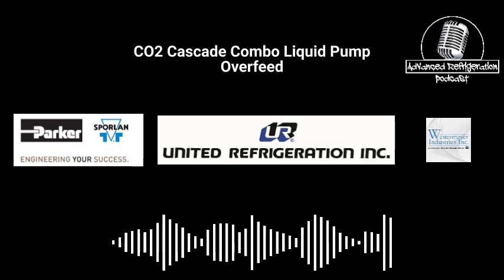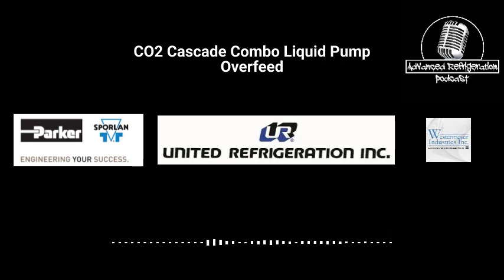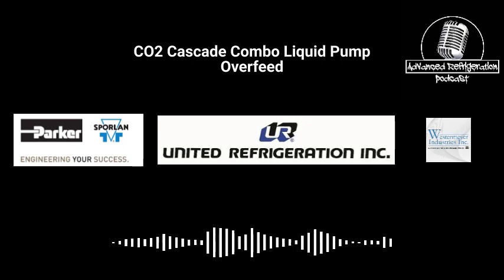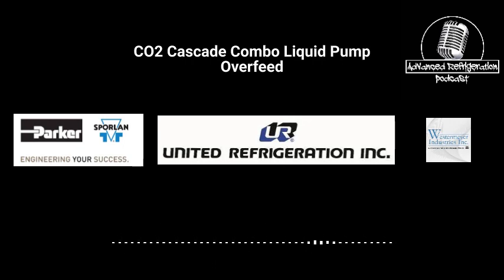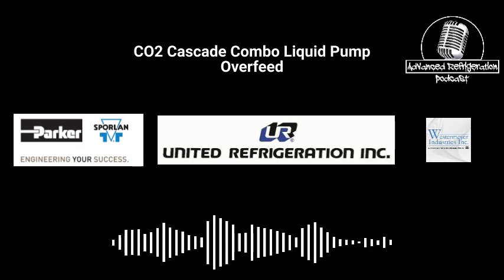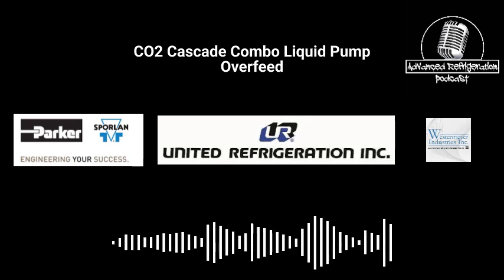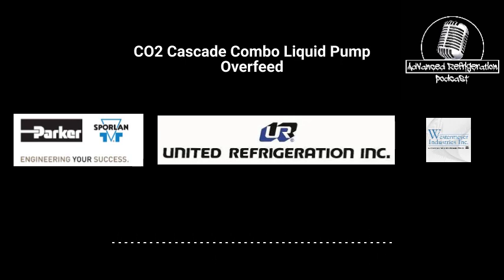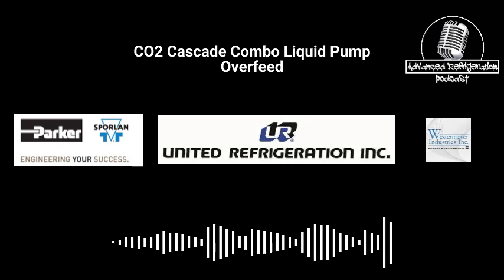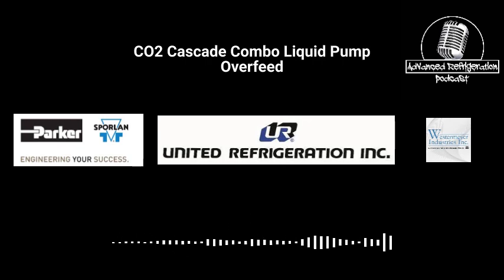XHP, I think. XHP. This is the Sporlan CO2 valves. Now, the solenoid valves, they're an orifice solenoid valve. You're either going to have those, the Danfoss ones, I don't know the part number on those, or you're going to have steppers. Now, on the medium temp side, think of it like a glycol.